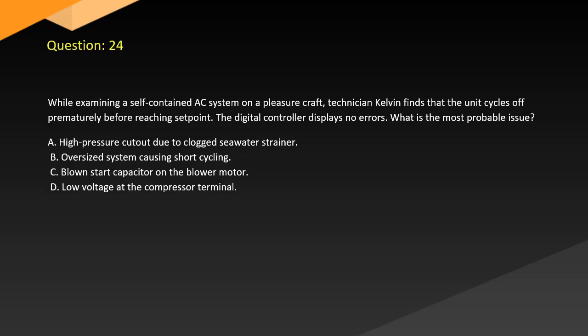Question 24. While examining a self-contained AC system on a pleasure craft, technician Kelvin finds that the unit cycles off prematurely before reaching set point. The digital controller displays no errors. What is the most probable issue? A. High pressure cutout due to clogged seawater strainer. B. Oversized system causing short cycling. C. Blown start capacitor on the blower motor. D. Low voltage at the compressor terminal.